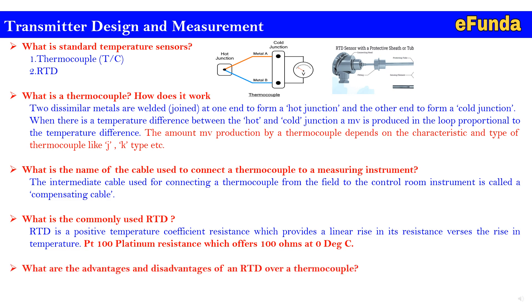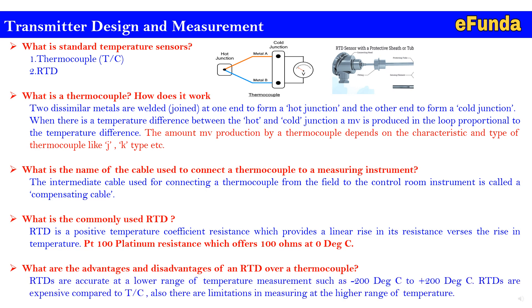What are the advantages and disadvantages of an RTD over a thermocouple? RTDs are accurate at the lower range of temperature measurement, such as minus 200 to plus 200 degrees Celsius, which is a narrow or lower band. RTDs are expensive compared to thermocouples and have limitations in measuring at higher temperature ranges, unlike thermocouples.